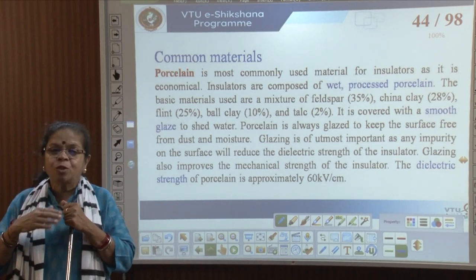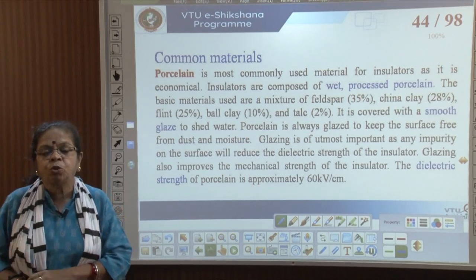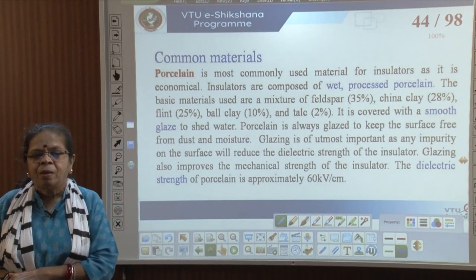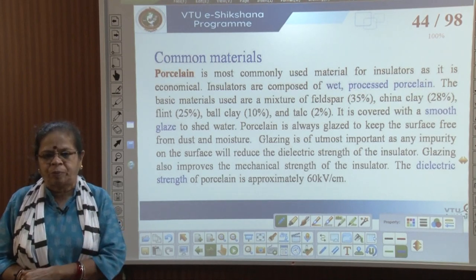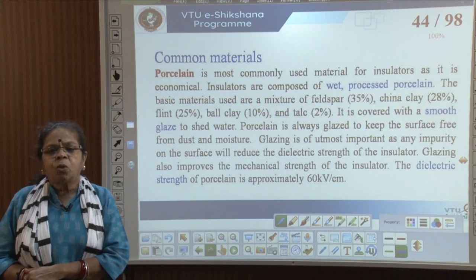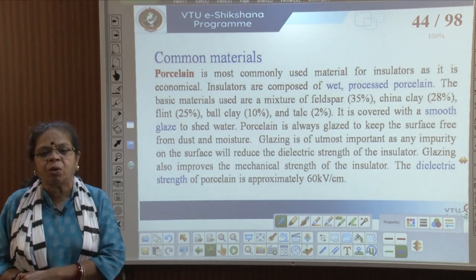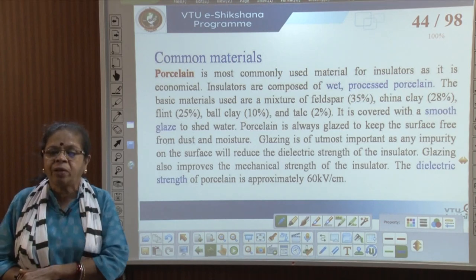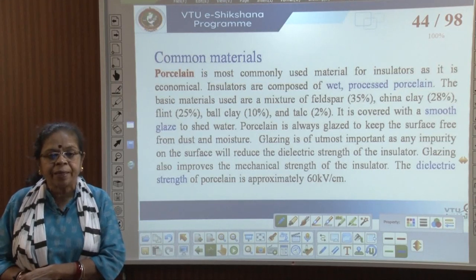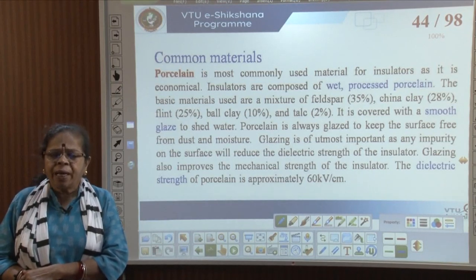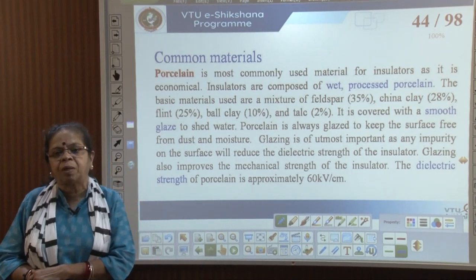The glaze is smooth so water does not stick to it — water slips away, shedding water from the surface. Glazing prevents the surface from accumulating dust and moisture. Any impurity on the surface would reduce the dielectric strength, and glazing also improves the mechanical strength of the insulator. The dielectric strength of porcelain is approximately 60 kilovolts per centimetre.